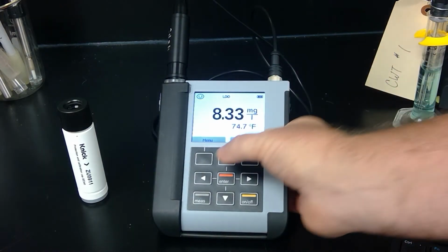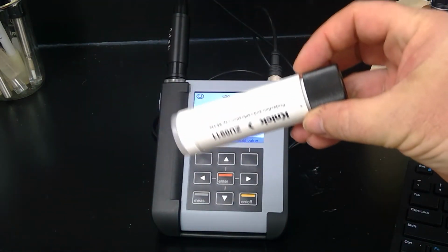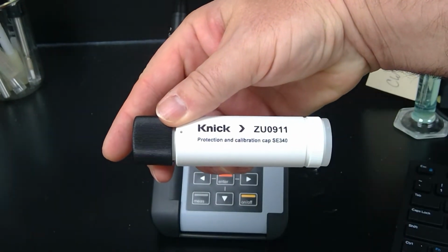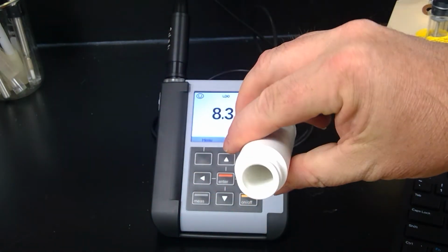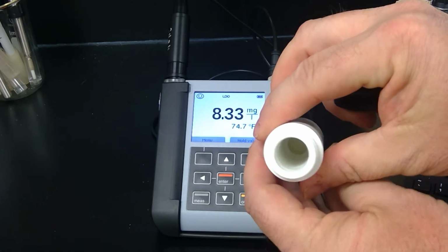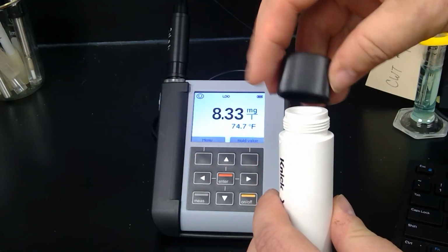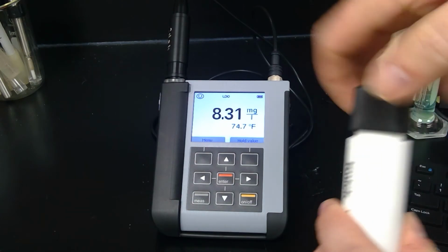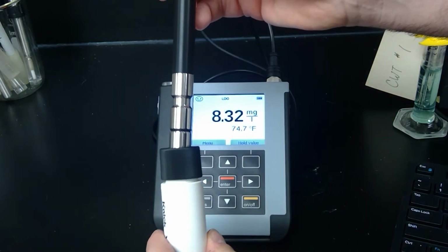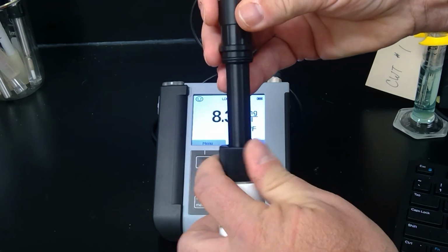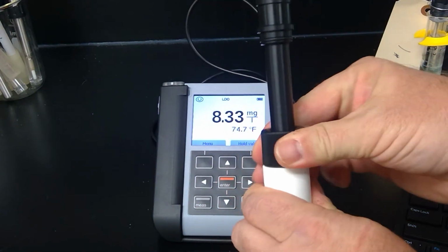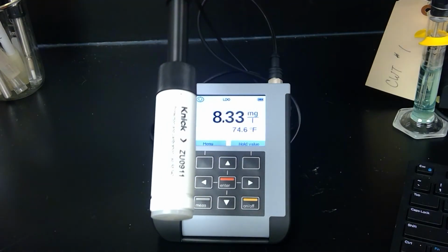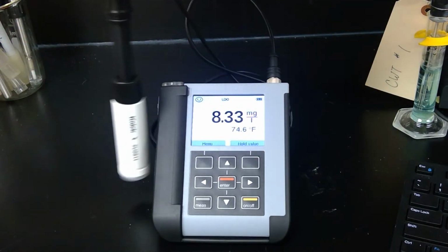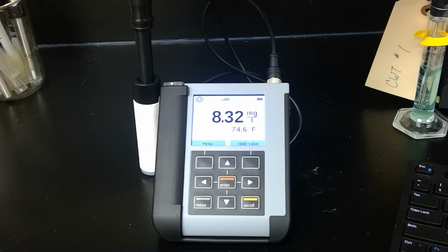So to calibrate, you would use this little calibration chamber or cap. The way this works is you take a little water, put it into the bottom. There's a small sponge, which is probably impossible to see, in the bottom. You thread this back on, take the sensor, and this is much like when you calibrate a 706, 707, or even an SE715, and it would also apply to the 740. And you put it in there with the moisture for about 20-30 minutes.